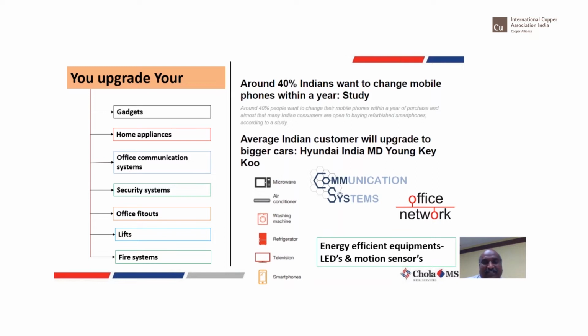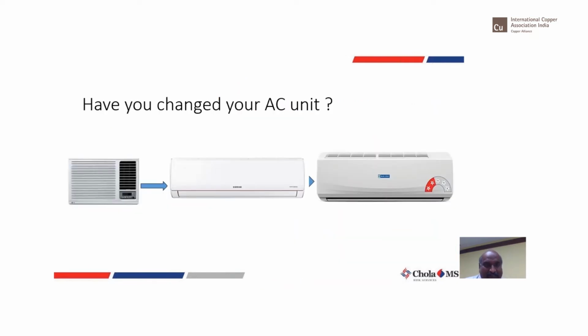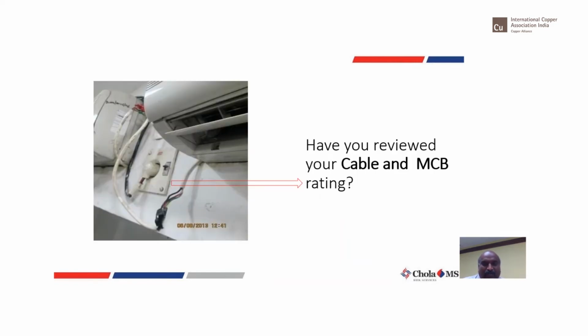There are chances where cables get heated, and one fine day they just melt. This is what is happening today in most homes and offices. People change the air conditioner, but what respect is given to the MCB and the cable being used? I'm 100% sure the MCB and the single pole metal clad socket box fixed on the wall are not changed, because you'd need to break the wall again, refix it, plaster it, and paint it.